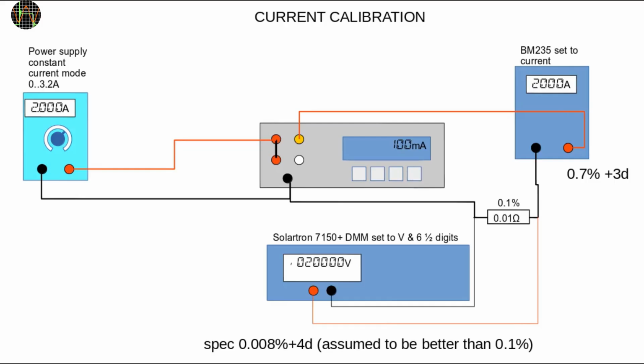But how do you do actual calibration? The basic setup is relatively simple. We need to run a reference current through PowerMon and compare the INA 219 current reading with a trusted multimeter that has the same current flowing through it. A power supply that can be set to operate in constant current mode helps a lot, and it allows the trusted current meter to basically be a short circuit to ground, and the various test currents are set on the power supply. If you don't have a power supply that can handle this, you can use power resistors as loads to get the currents you want, but it becomes much more time consuming and the resistors may get very hot.